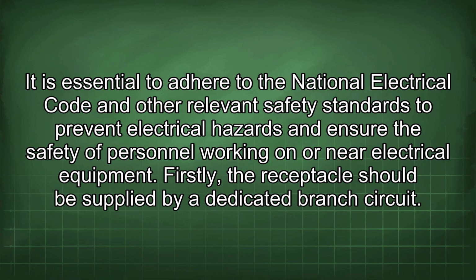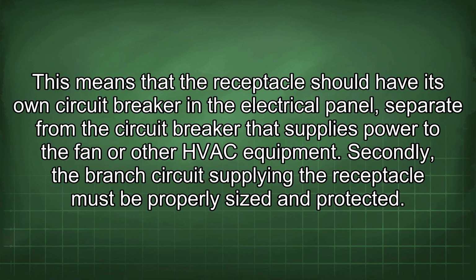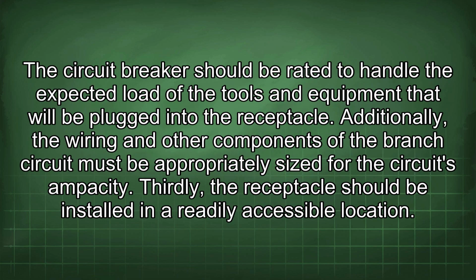Firstly, the receptacle should be supplied by a dedicated branch circuit. This means that the receptacle should have its own circuit breaker in the electrical panel, separate from the circuit breaker that supplies power to the fan or other HVAC equipment. Secondly, the branch circuit supplying the receptacle must be properly sized and protected. The circuit breaker should be rated to handle the expected load of the tools and equipment that will be plugged into the receptacle. Additionally, the wiring and other components of the branch circuit must be appropriately sized for the circuit's ampacity. Thirdly, the receptacle should be installed in a readily accessible location.